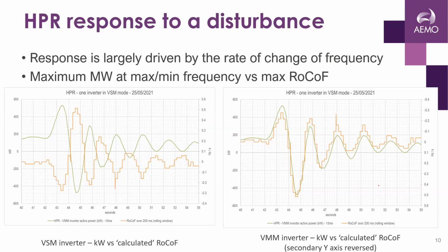It's hard to see on the screen, but I'll try and explain a little bit slowly here. There are two graphs here. Let's focus on the graph on the left-hand side, where the green one is the response. I should probably say that this is the response of one inverter. We had a trial of two inverters in grid forming mode for quite a long time. While the trial was ongoing, there was a frequency disturbance, and we recorded the response from that one inverter. The one on the screen on the left side is the response from one inverter in virtual synchronous machine mode. The green one is the megawatt, and the orange one is the rate of change of frequency, which I have calculated on a 200 millisecond rolling window average.